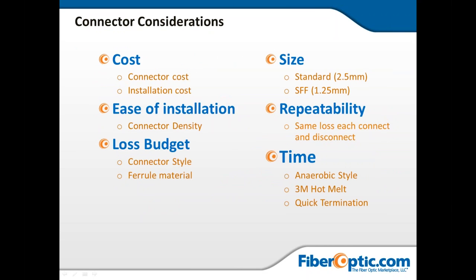Considerations when choosing connectors: cost, installation, budget, and size — 2.5 mm versus 1.25 mm ferrules. Going down in ferrule size gives you more real estate. Repeatability: each time you mate the connector, does it give you the same results? And termination method: do you have the ability to do quick termination with a splice-on connector, or do you epoxy and polish, or splice on a pigtail, or use the anaerobic style — a quick-melt hardening epoxy?